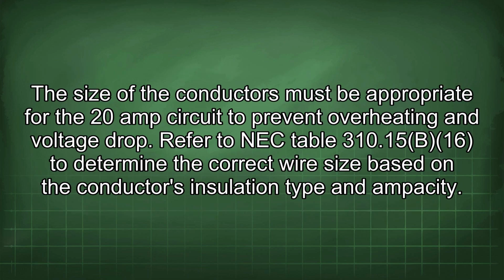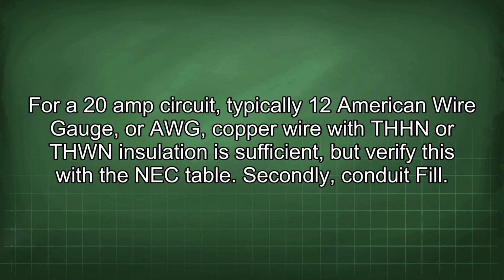The size of the conductors must be appropriate for the 20-amp circuit to prevent overheating and voltage drop. Refer to NEC Table 310.15(B)(16) to determine the correct wire size based on the conductor's insulation type and ampacity. For a 20-amp circuit, typically 12 American Wire Gauge, or AWG, copper wire with THHN or THWN insulation is sufficient, but verify this with the NEC table.